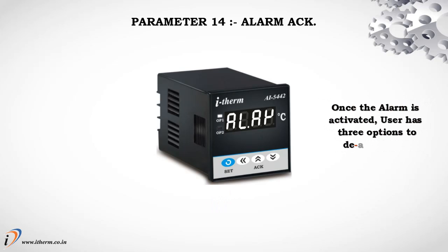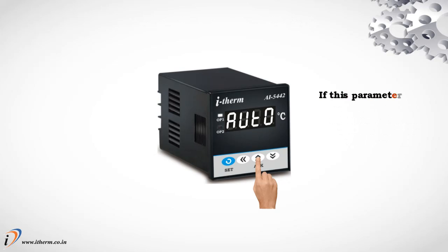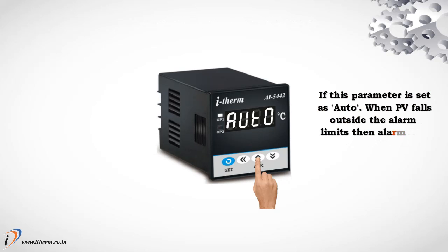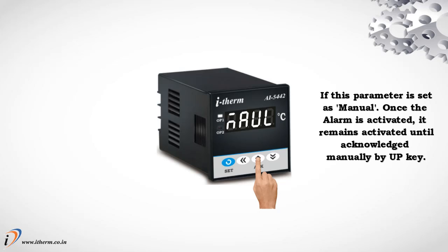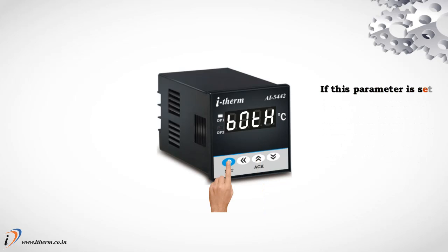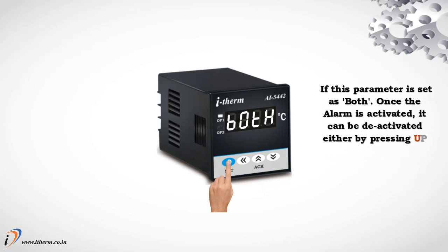Parameter 14. Alarm acknowledged. Once the alarm is activated, user has 3 options to deactivate it. If this parameter is set as auto, when process value falls outside the alarm limits, then alarm will be deactivated automatically. If this parameter is set as manual, once the alarm is activated, it remains activated until acknowledged manually by up key. If this parameter is set as both, once the alarm is activated, it can be deactivated either by pressing up key or when process value falls outside the alarm limits.